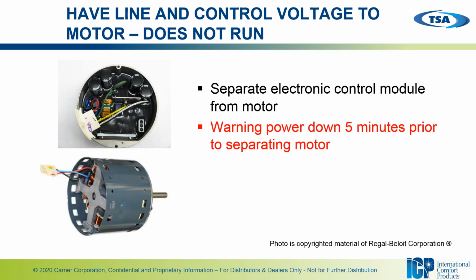Okay, so what do you do if you have your high voltage to the motor and you have your control voltage to the motor, but it still doesn't run? You can separate the module from the motor, and we will forewarn you: power it down and wait 5 minutes before separating, because there are very, very high voltage capacitors in that module that could do some pretty serious damage. So when we give you this warning, it is pretty serious.